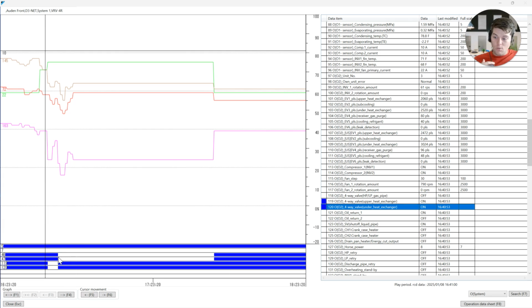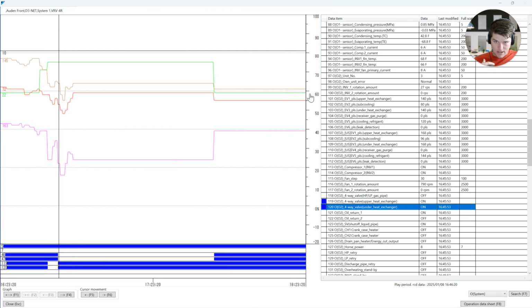How long is that? Well, I can click here and I can see my timestamp, which is located down here in the bottom right, is 1646. And then I can go back and I can click here and it is 1747. This is an hour long, not just an hour long snippet between the 2. This is an hour long defrost. Wow. 60 minutes of continual defrost, right? That's a marathon of defrost.